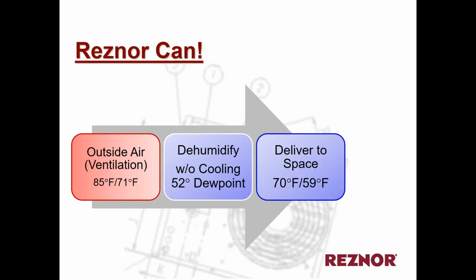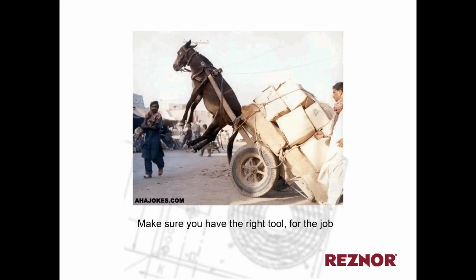So essentially what we're doing, we're taking that outside air, we're doing a pretty good job of dehumidifying with that energy recovery wheel before it ever hits the heat pump side, and it's designed to deliver air in a 70-degree discharge condition at about 45% relative humidity. So we want to make sure that you are picking or selecting the proper product for the job, and that's kind of where we are to help John and Wayne and myself.